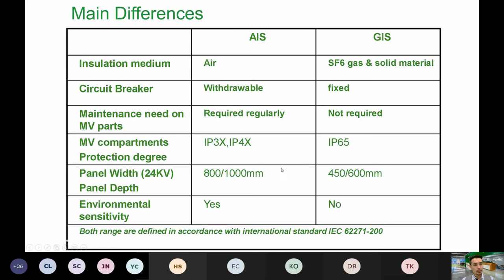So for those who are not familiar with IP ratings, the first digit talks about solid particles, and the second digit talks about water ingress. So you can see in here for AIS, there's no water ingress protection. Right, there's only solid particles for the first digit. Whereas for GIS, they have both. Right, the footprint is much smaller for GIS. Just one limitation is that the SF6 gas is not environmentally friendly.